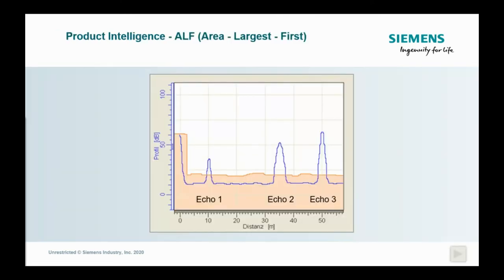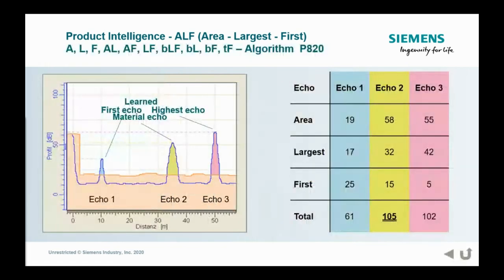Okay, so let's talk about the world of when you don't have one single echo, right? Here's a case where I've got an echo profile. I've got three echoes, echo 1, 2, and 3. There is something in product intelligence which is talking about how it evaluates these different echoes, and it evaluates them on three different values: area, the largeness, and the firstness, if I can make up words. And what it's going to do is apply a numerical score to all of the valid echoes based on three criteria. Number one is, what is the area underneath the curve between the peak and the TVT?